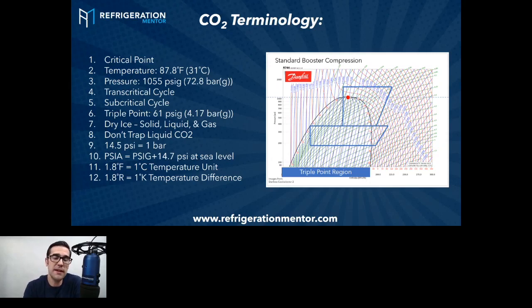So one thing you're going to hear about CO2 is something called the transcritical cycle. And really what that means is that you're running above the critical point. And this is where CO2 heat pumps are going to be running, because you're getting a lot of heat at that point to heat up that water or heat up that air, whatever the design of the system is. And we're going to talk about different designs, from residential units all the way up to commercial and industrial units. But you need to understand that.